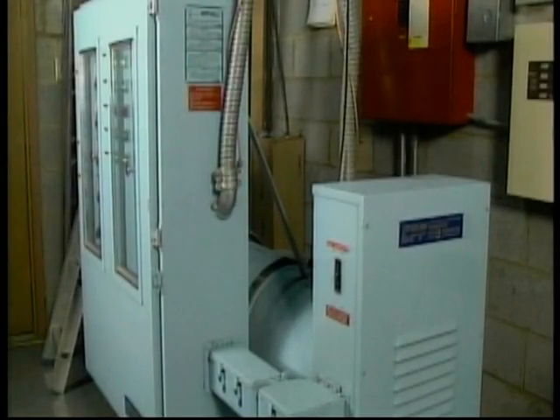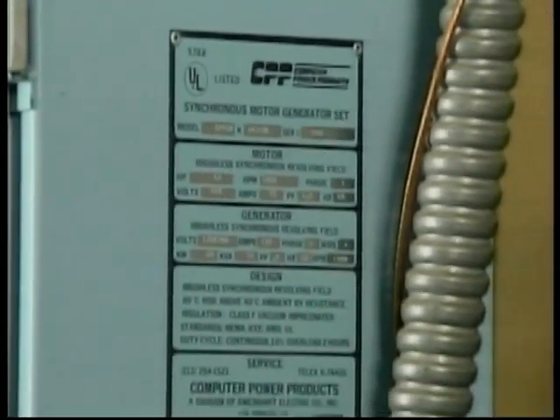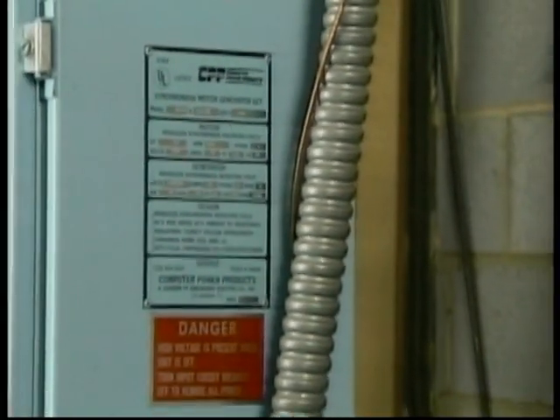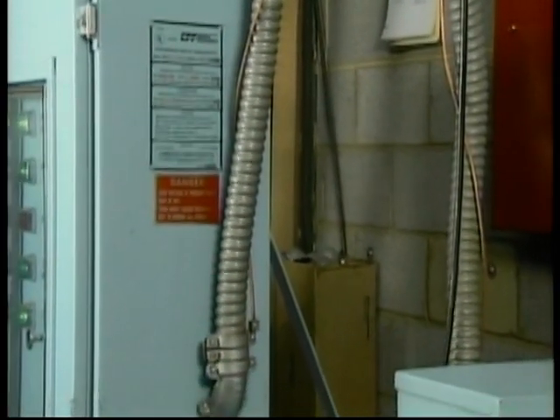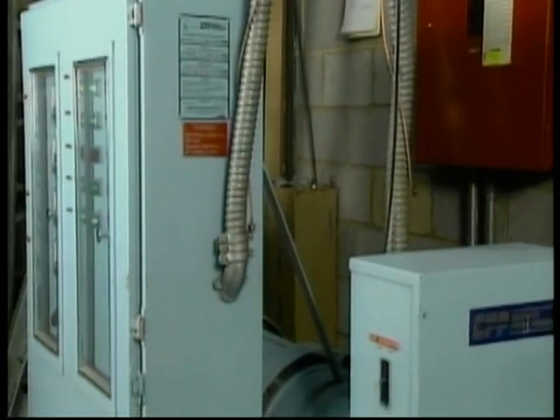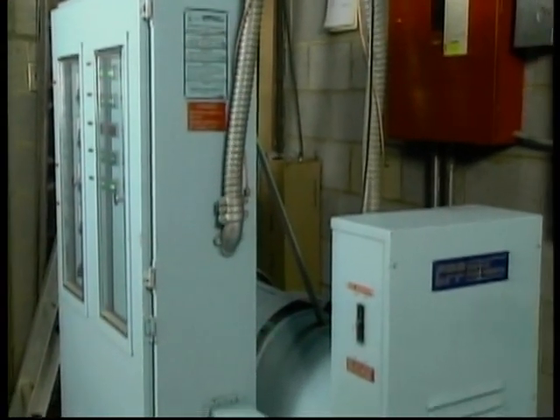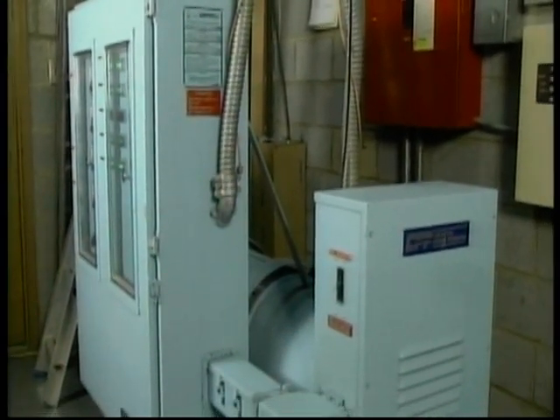A motor generator, or MG set, consists of a drive motor mechanically connected to an AC generator. An MG set generates a new voltage waveform for the load, isolating it from disturbances on the power system. It can also help shield a load from sags, swells, and surges because of the inertia supplied by the motor.